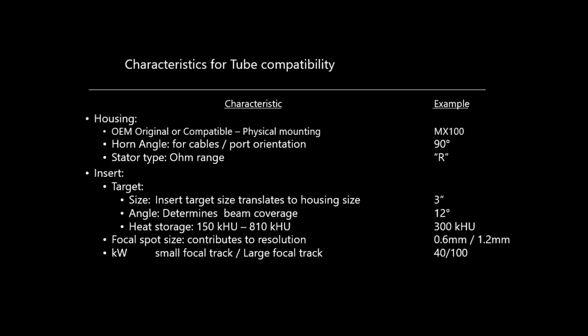You have the stator type, and the stator type is typically measured in ohms. There's probably half a dozen common stators, and you want to have the stator so that you have the anode spinning at the correct speed. The insert, so you want the target. Biggest thing is the size. So we generally talk about 3-inch and 4-inch targets. That's different ones around. Here's a 3-inch target.